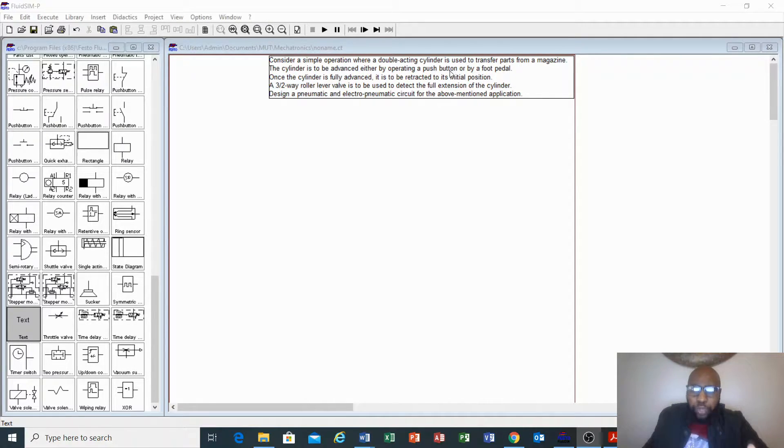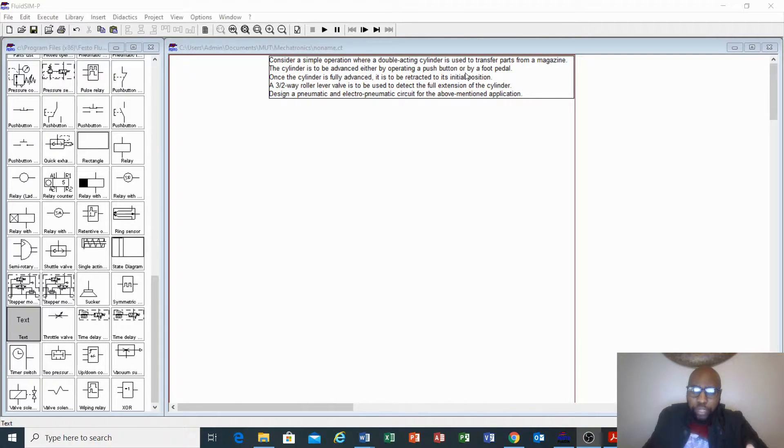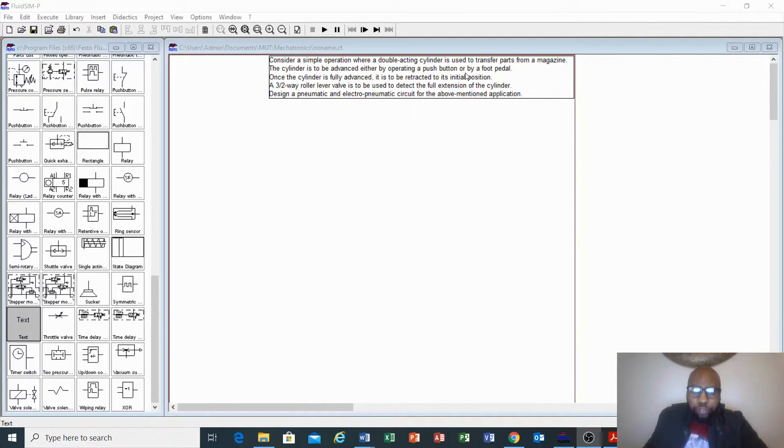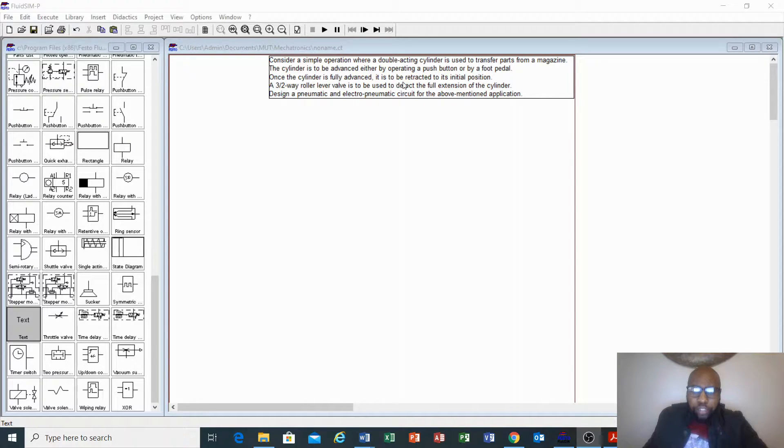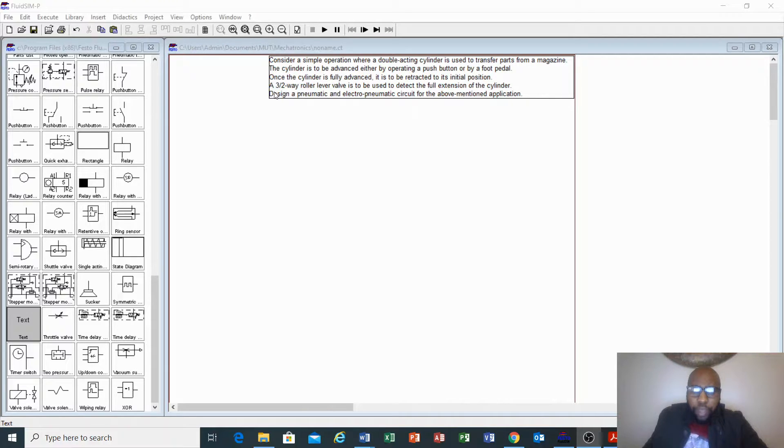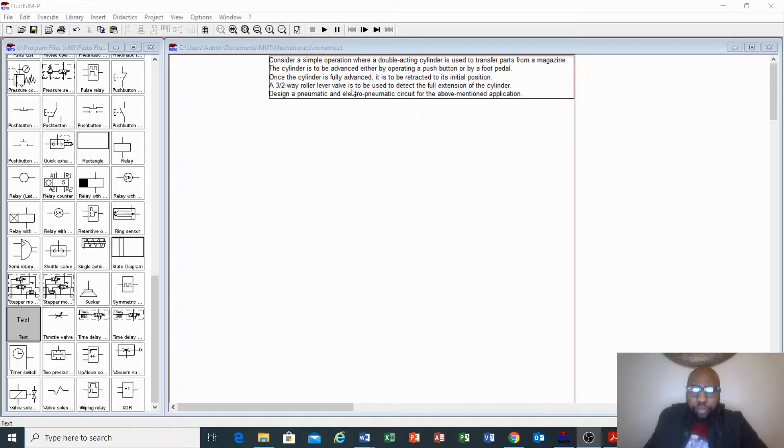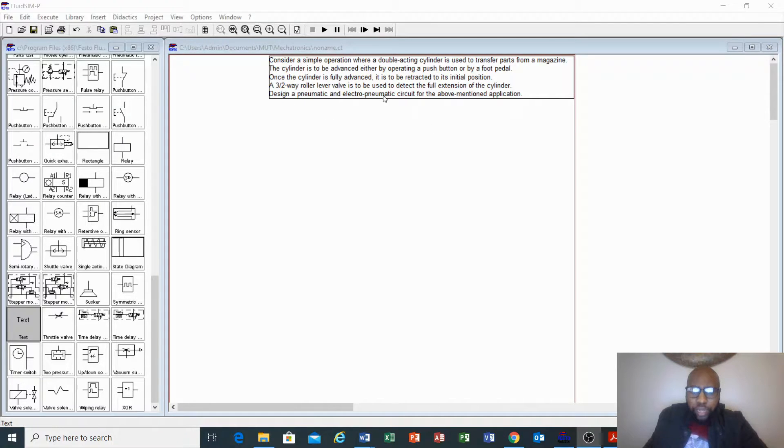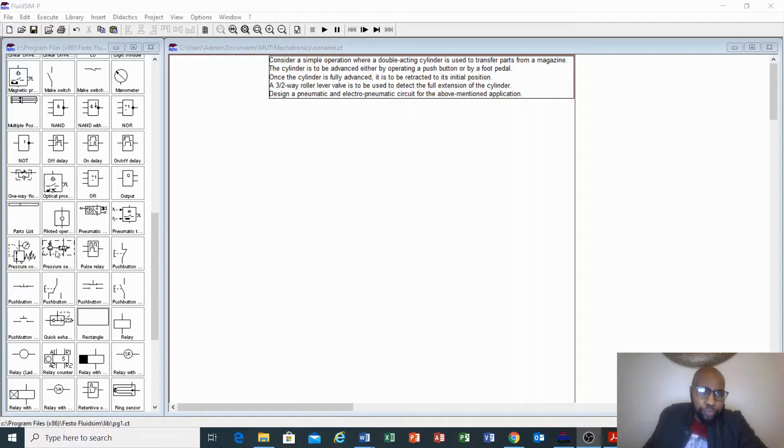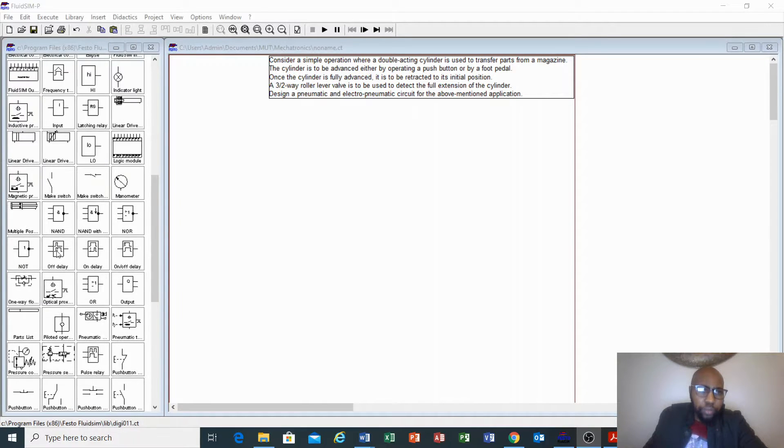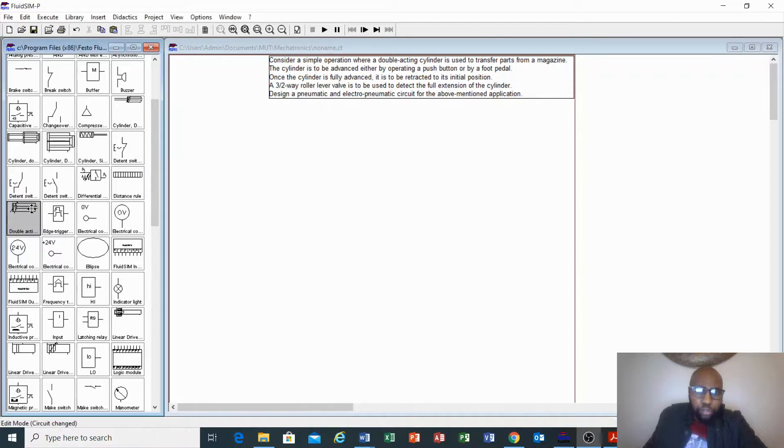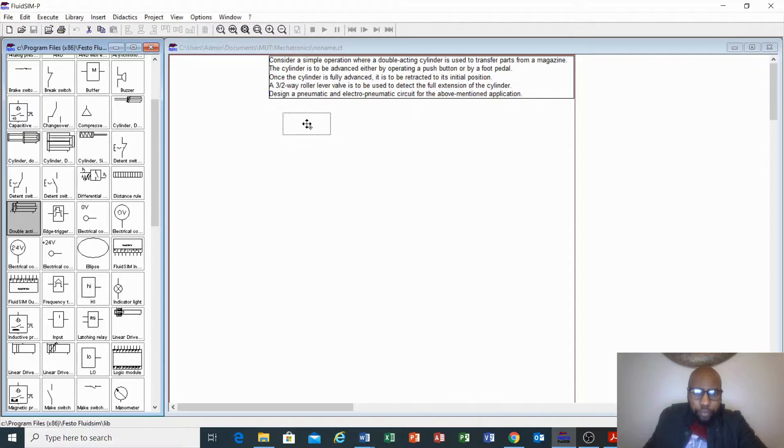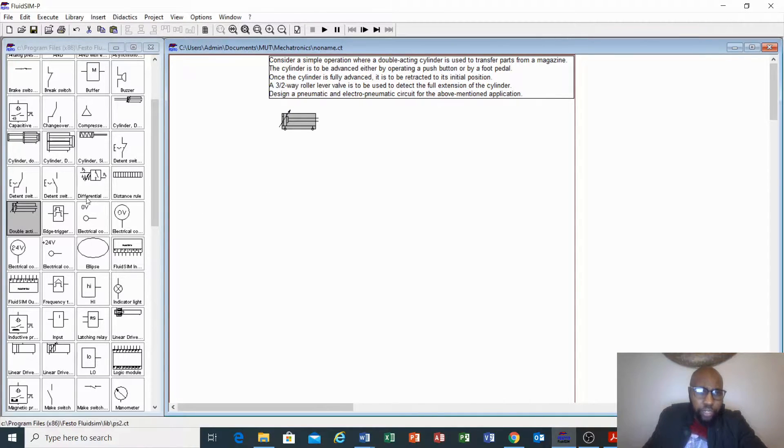So here we have a push button, a foot pedal, and you must connect this using a shuttle valve or an OR valve. Once the cylinder is fully advanced, it is to be retracted to its initial position. A two-way lever is to be used to detect the full extension of the cylinder. Let us quickly do the pneumatic first, then we can design the electro-pneumatic.